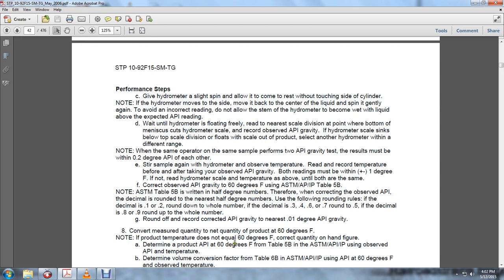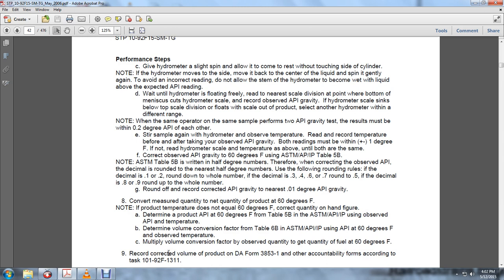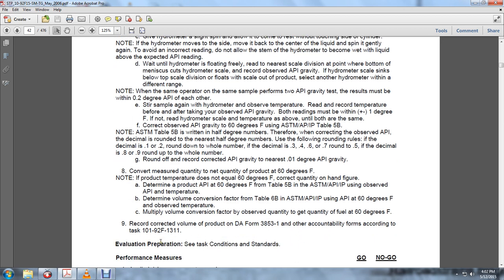Determine the API degree at 60 degrees Fahrenheit from Table 5 of the ASTM API IP, using the observed temperature. Determine the volume conversion factor from Table 6 of the ASTM API IP. Using the API gravity at 60 degrees Fahrenheit, the observed temperature, the volume conversion factor and the observed quantity, quantify the fuel at 60 degrees Fahrenheit. Record the current corrected volume of the product on DA Form 3853-1, accountable according to the task.